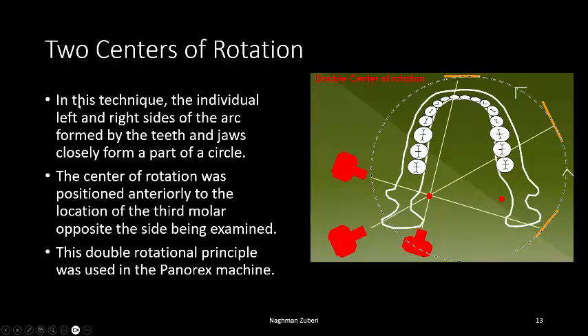For two centers of rotation: the individual left and right sides of the arc formed by the teeth and jaws closely form part of a circle. The center of rotation was positioned anteriorly to the location of the third molar, opposite to the site being examined. When examining one side, the center is on that side, and when examining the other side, the center shifts accordingly. This double rotational principle was used in the Panorex machines.